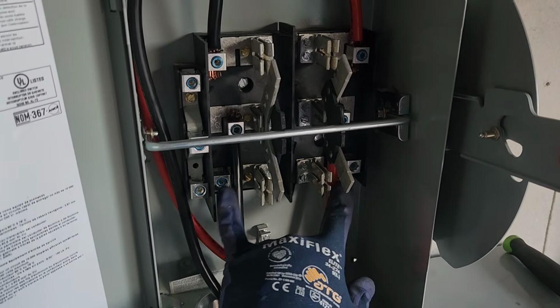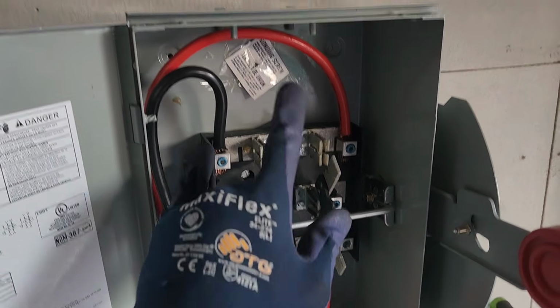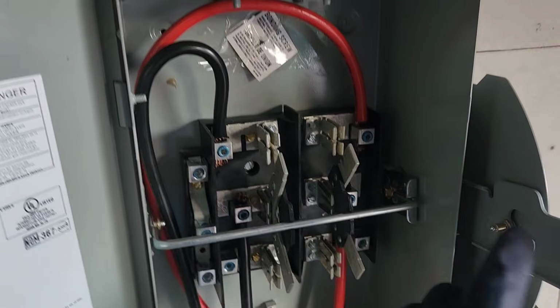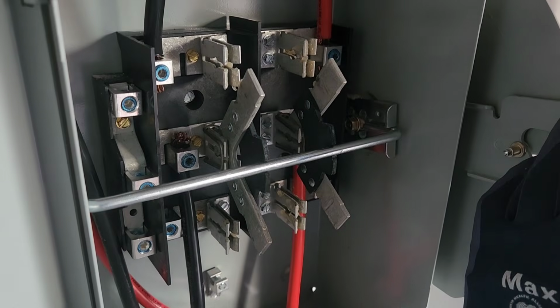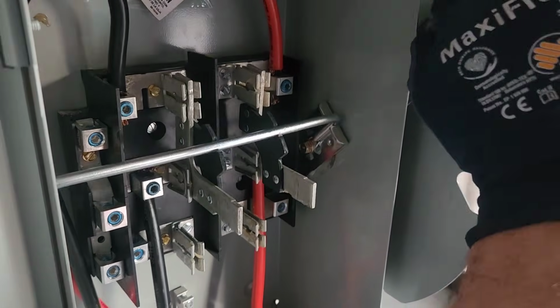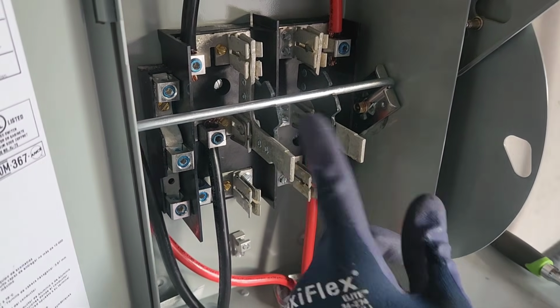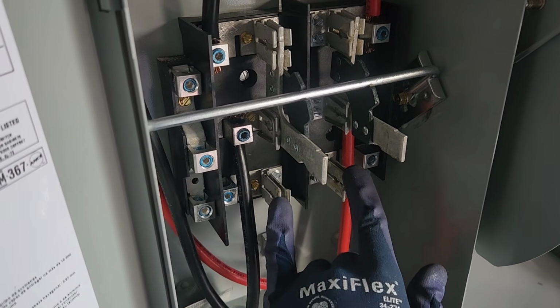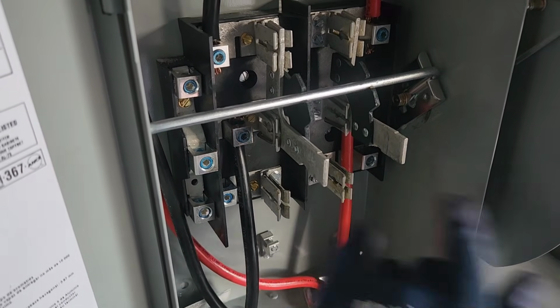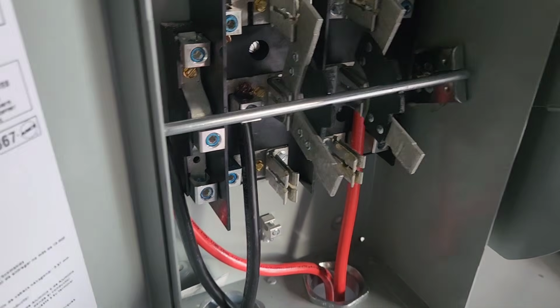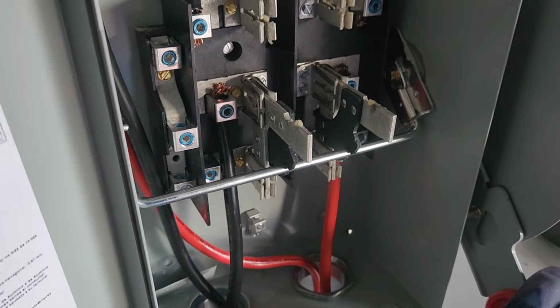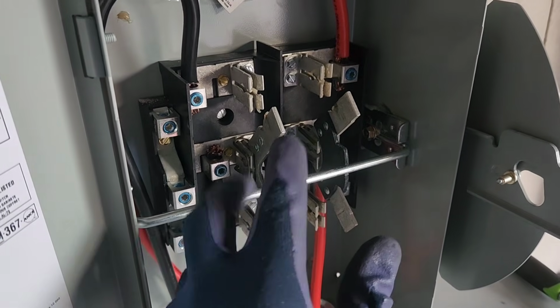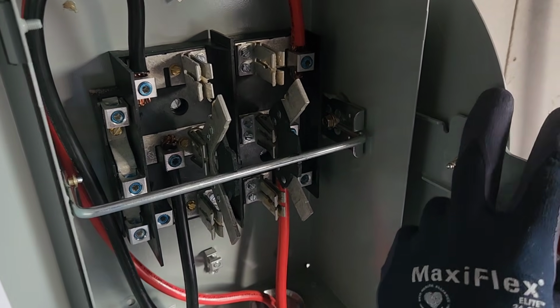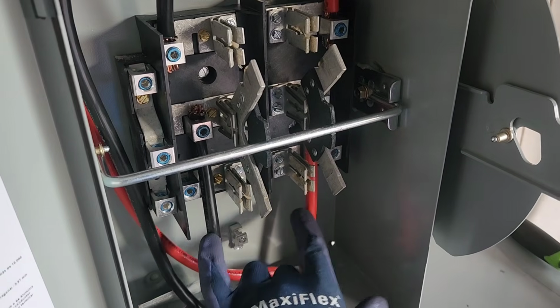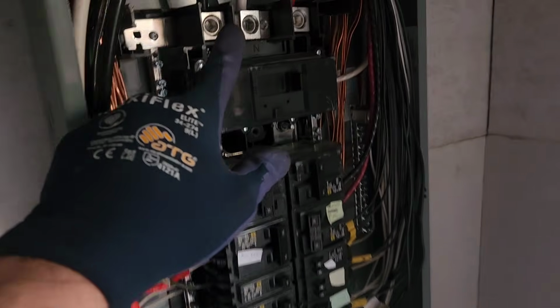So I've got these two feeding into the top of my panel and these two coming from the grid. If I want to go to the grid, I just pull this handle up and it makes that connection. I could hook my solar generator or solar inverter output here - if I want to go to solar, I feed from solar. So connected to the top or the bottom will determine what feeds the top of the panel - those hook into the top of the panel.